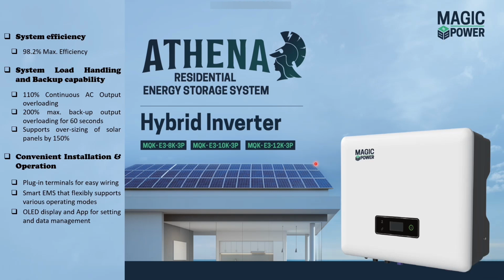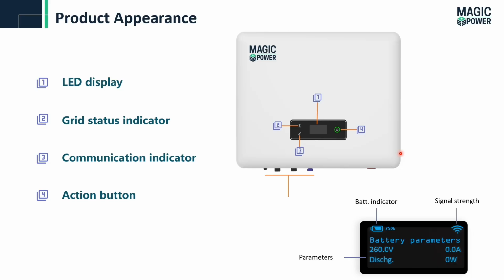Next, we look at the appearance of the system. Here we can see the LED display, the grid status indicator and communication indicator. Here is the action button. Basically, the grid status indicator shows whether the system is connected to the grid or not, and the communication indicator shows that it is communicating between the BMS, the battery management system, and the smart meter connected to the system.